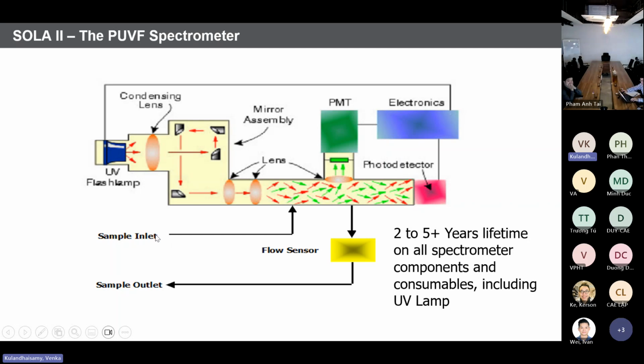So in your process, after the combustion from the pyrolyzer, the product will go to the bench. The green color ones are the SO2 molecules. When the SO2 molecules get energized by the UV light, then whenever they go to the de-energized state, they will emit photons. Those photons can be captured by the photomultiplier tube. Then it will convert the photo signal to an electronic signal. Finally, the electronics process the electronic signal to the ppm level or ppb level.